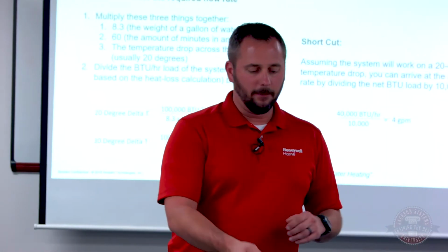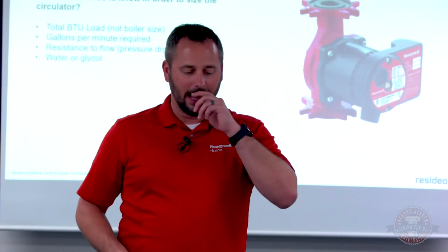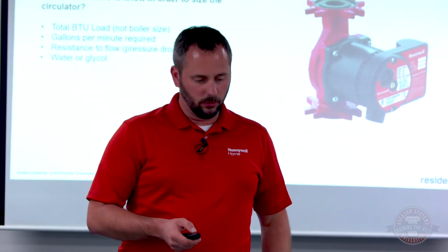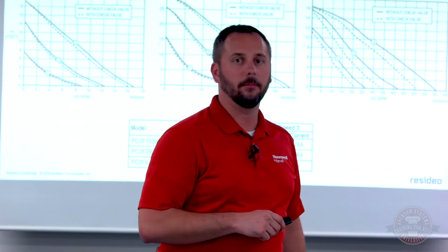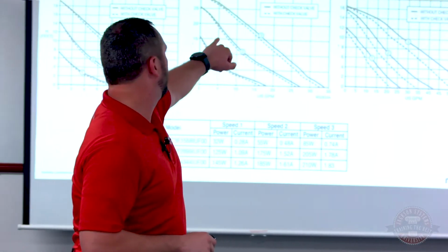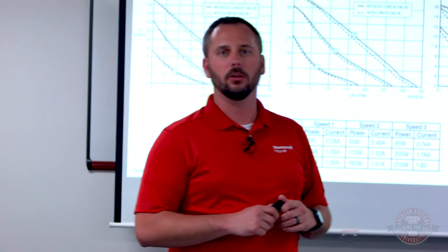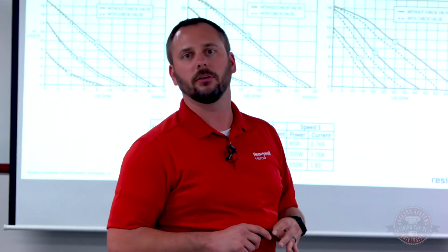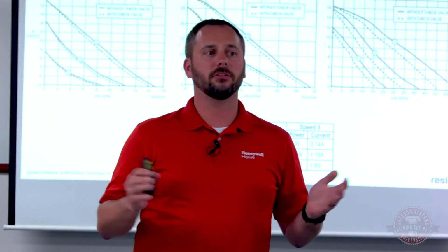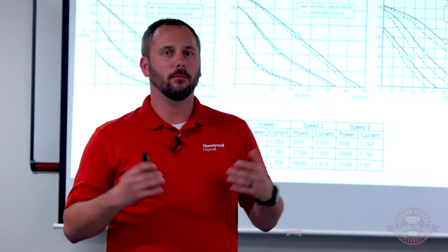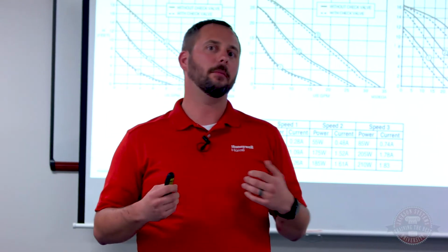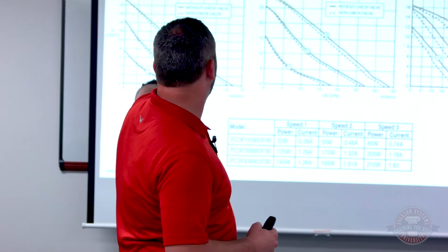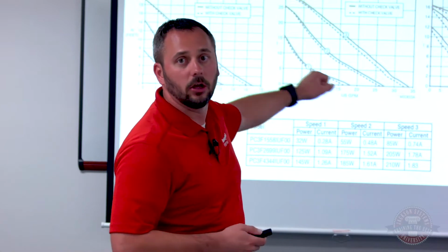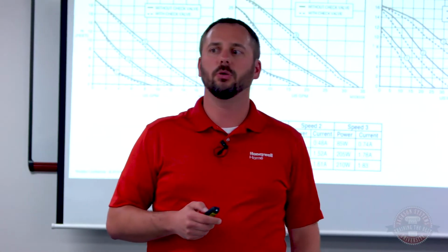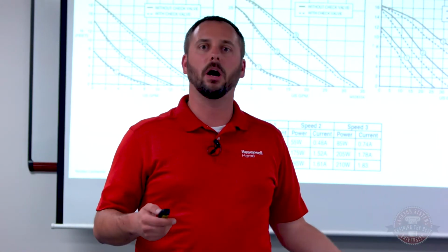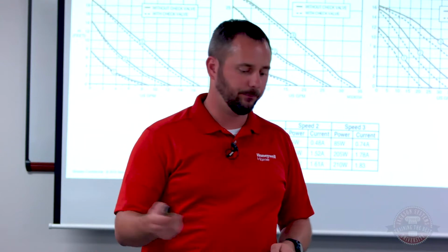So I'm going to jump backwards real fast. I'm going to jump around to my slides to the pump curves again. So when we looked at the pump curves, there's always two sides you've got to look at. You've got the x-axis and the y-axis. So you've got flow rate listed on one of them. You've got pressure on the other. So we just came up with the flow rate. So if we were to trace the number, we kind of know where we've got to look on that. But now we've got to come up with the pressure to identify really where we need to be, and which pump and which speed we need to run it on.